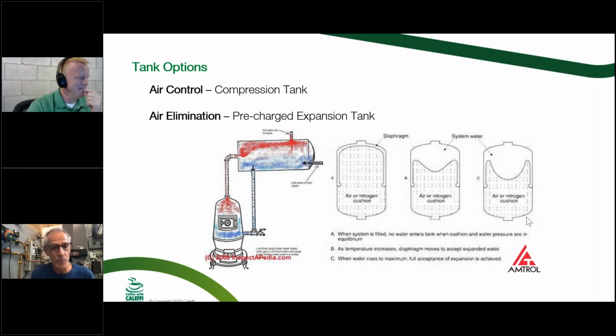And here's probably two of the most common systems that you're going to come across out there. One on the left there is called a compression tank, or sometimes called a plain steel tank. And it is that. It's just a tank that has some water and some air in it. And they're still around. You can still buy these tanks. They're getting pretty pricey these days. And that is what's called an air control system.